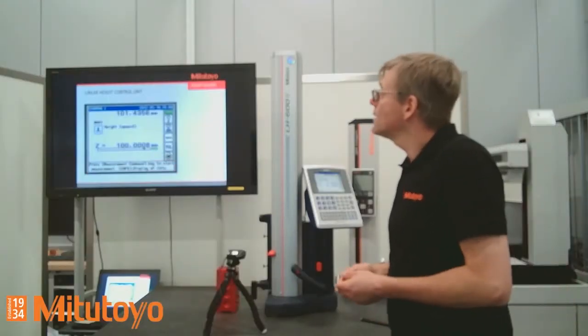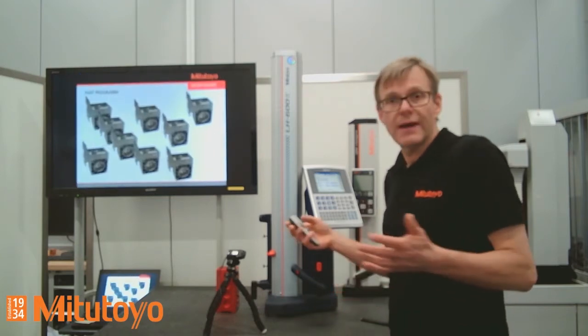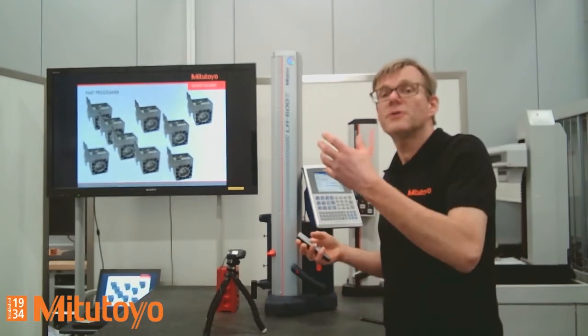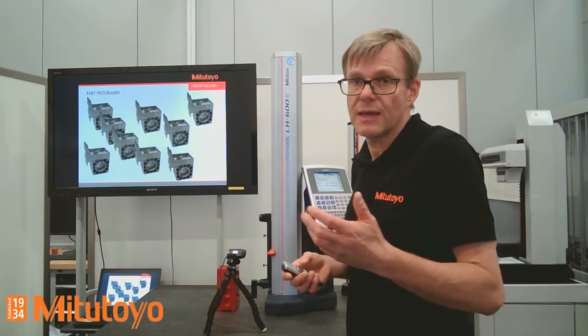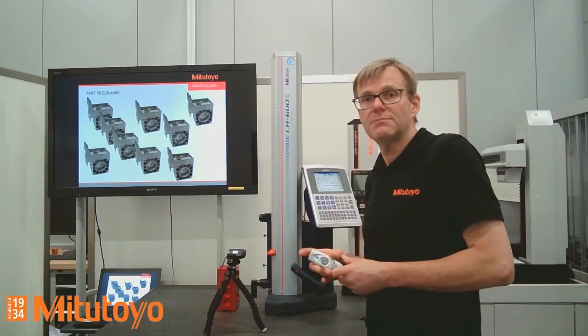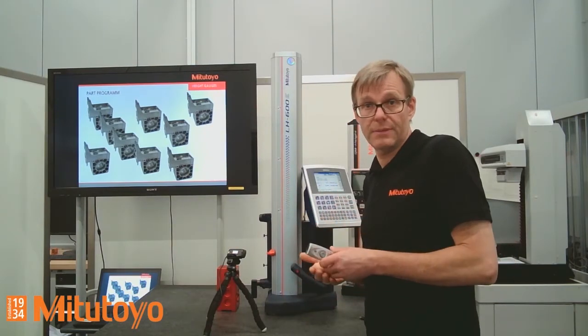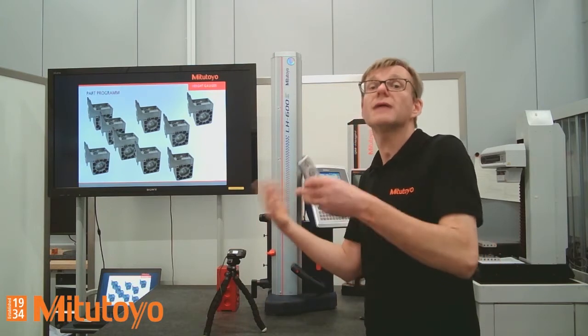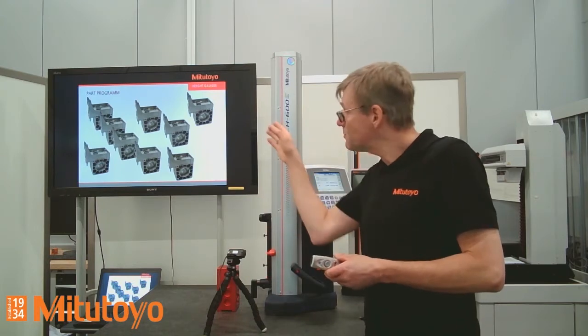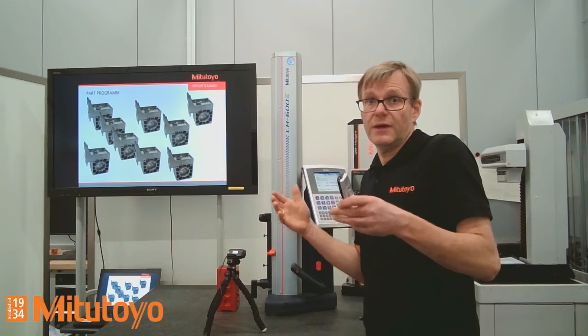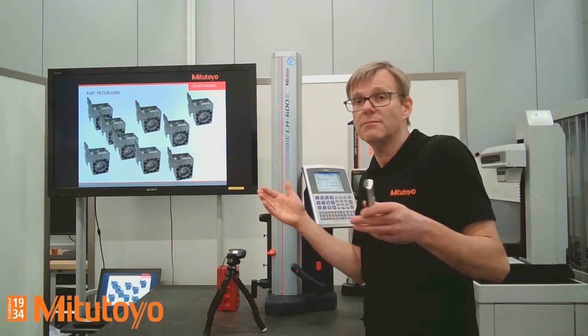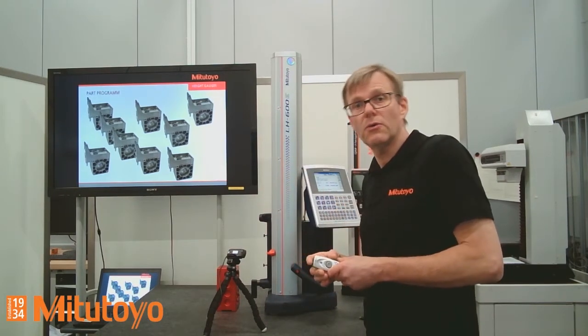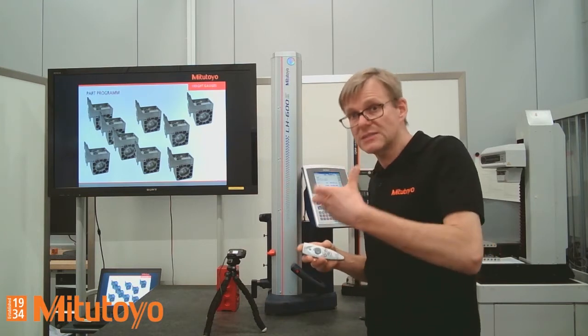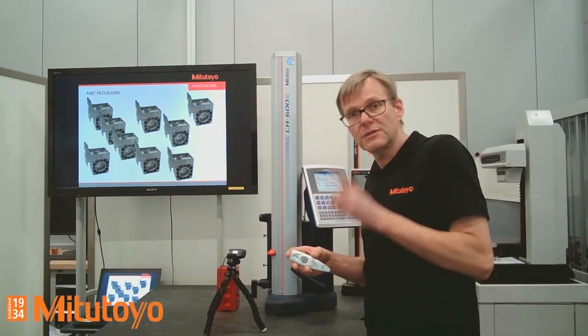The next step is, if the customer has many work pieces of the same kind, then it makes sense to write a part program, because later on you would like to execute the part program. All these parts have the same features, some diameters, some heights to measure. So then it is best to write a part program. And this I would like to show you.